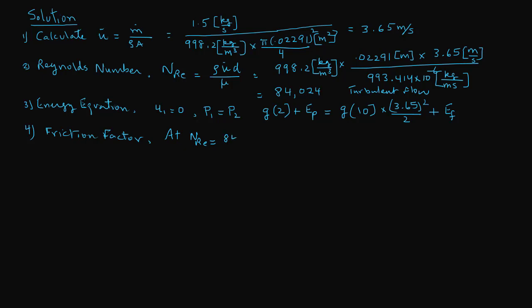At a Reynolds number of 84,024 and assuming the pipe is smooth (relative roughness equals zero), either from the Moody diagram or through spreadsheet calculation, we obtain the friction factor as 0.0046. Now we determine the various frictional terms in this system.